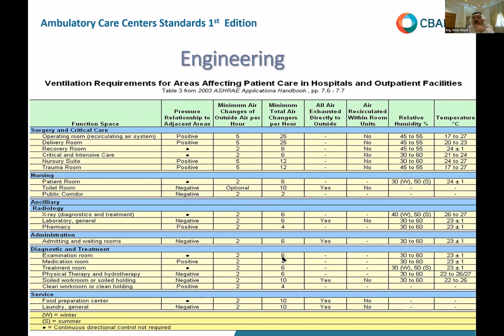The air changes within the room have to be 6 times. So we need to calculate from your air handling unit or your conditioning how many air changes happen in each hour. So you need 6 air changes. So we have 8 air changes, 2 fresh and 6 recirculating. Why is he asking for recirculating air? The more air changes you do, the less settlement of bacteria and germs will be on the surfaces. The higher the air changes in any room, the minimum settlement there will be on the surfaces within the room. That's why we emphasize.